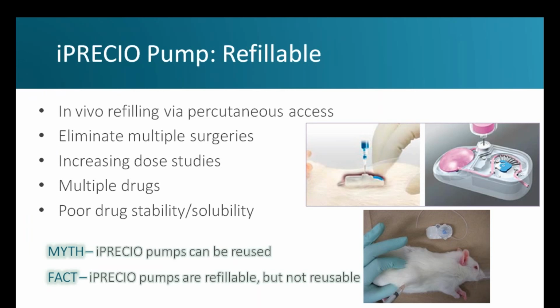The ability to refill the reservoir is also helpful when testing multiple drugs or when working with drugs that have very poor stability or poor solubility that require to be formulated or prepared fresh for dosing very often. Although the iPRECIO pump is refillable, a common misconception is to incorrectly assume that it can be reused. And just like the ALZET pump, the iPRECIO pump is designed to be a disposable product for single use. It's important to note that the battery life is the main limiting factor preventing the iPRECIO pump from being reused. Sterility and the potential for cross-contamination is also another issue to consider.